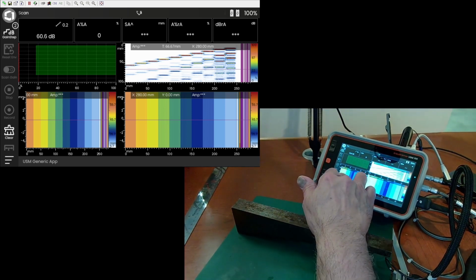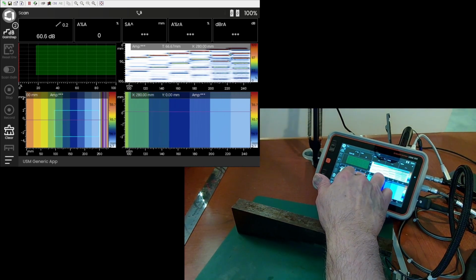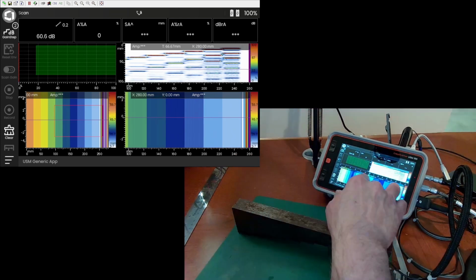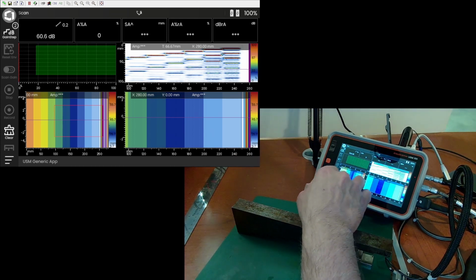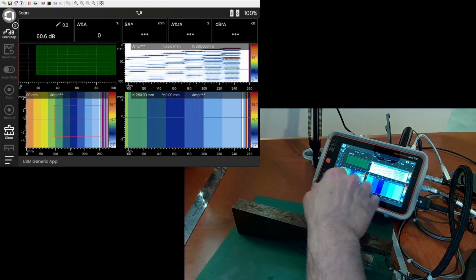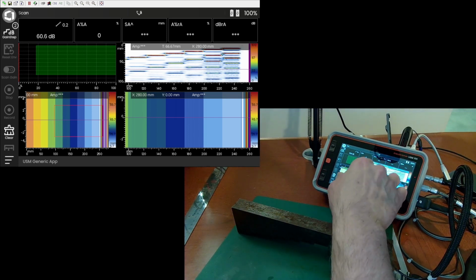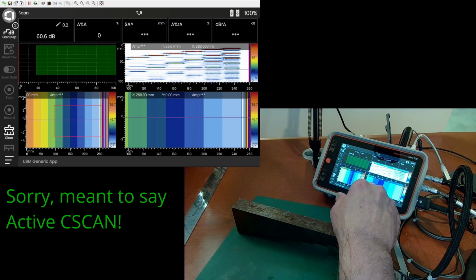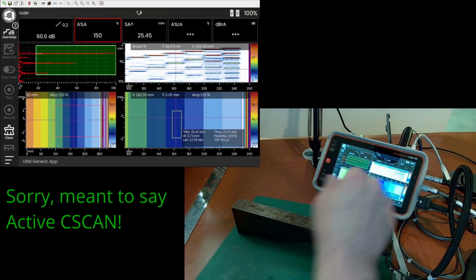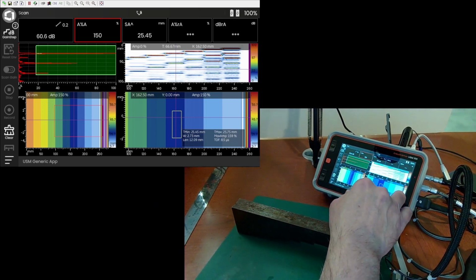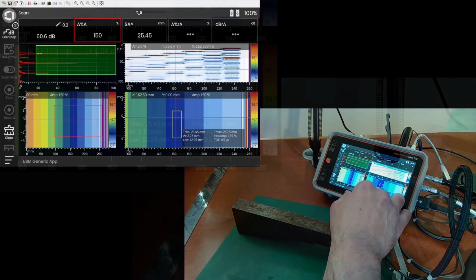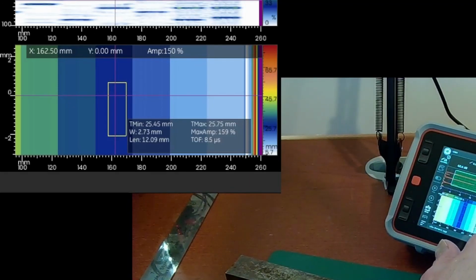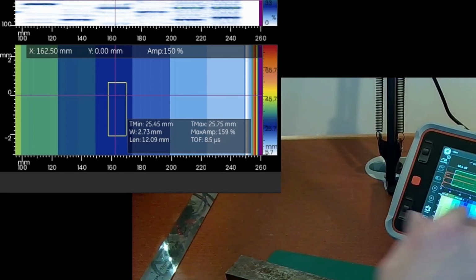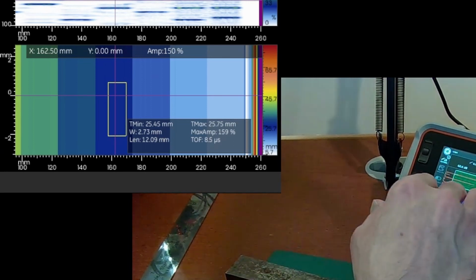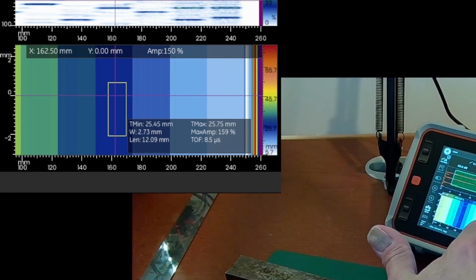So let's see, we can select an area here, have a look at the active part of the CSCAN, and you'll notice what's highlighted by the box here is what is selected for width on the active CSCAN and on the BSCAN. Now on the BSCAN, I can draw a box. The crosshair will snap to the highest amplitude that's seen within the box, and we get some information. So I see that my min thickness is 25.4, my max thickness is 25.75. So that is looking at minor variations within the box of thickness.